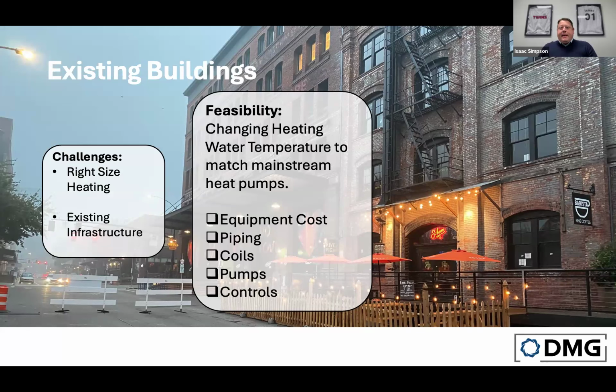The boilers are probably oversized due to factors of safety on top of factors of safety, and we need to figure that out. If we just looked at the nameplate value of that boiler and tried to buy a heat pump to fit that, it would be way oversized, probably way out of budget, and we wouldn't have the electrical, physical, or other space needed to make that work. So the first challenge in decarb, whether it's a traditional heat pump or a new CO2 heat pump, is right sizing.